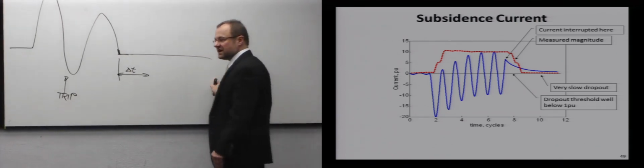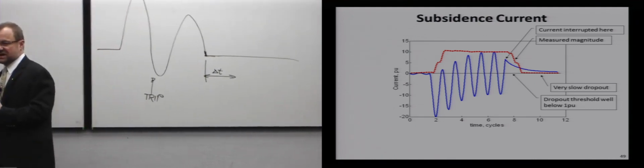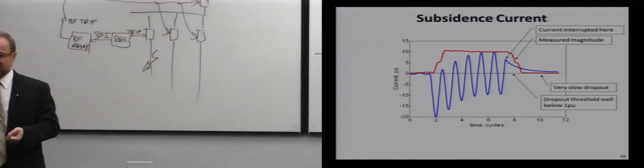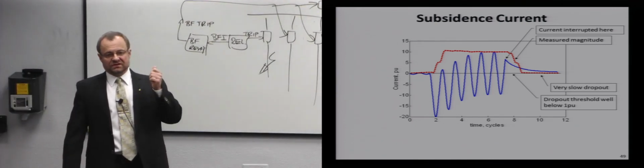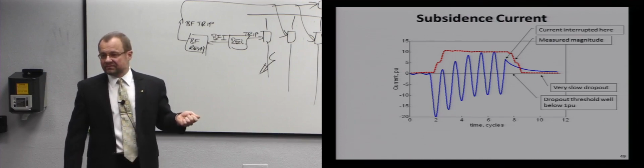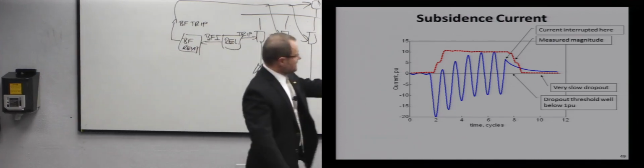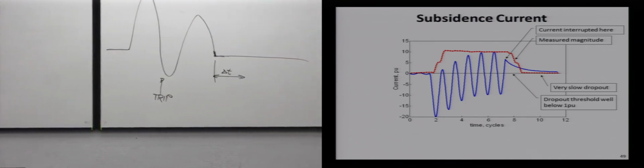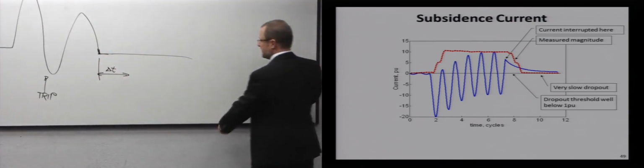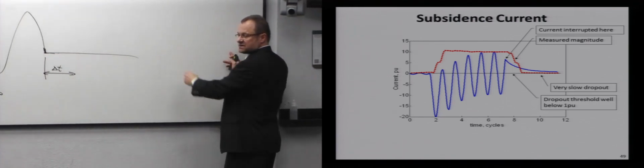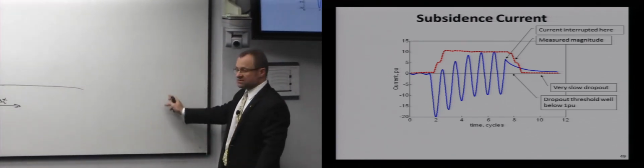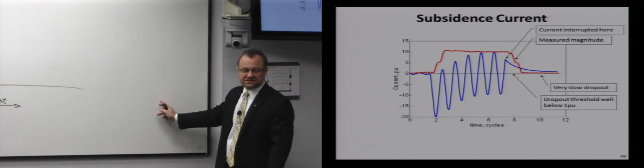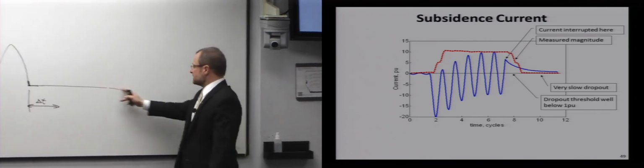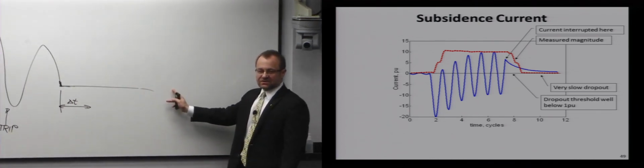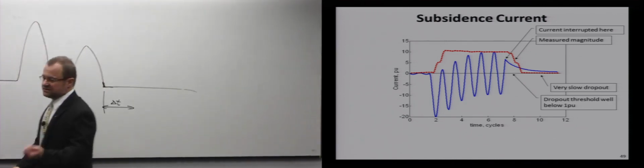But what is the problem with that? I have a critical fault clearance time, meaning that my power station people will say that any fault needs to be cleared within 10 cycles or else we go black. So from here to my 10 cycles, I have to squeeze 2 trips. I have to make sure that I trip the main breaker and then I trip the other breakers. So under the contingency that the breaker failed, everything really ends after 10 cycles. Because if it doesn't, we go black. So waiting up to here to realize that the breaker fail actually opened is not an option. So we want to have a fast reset.